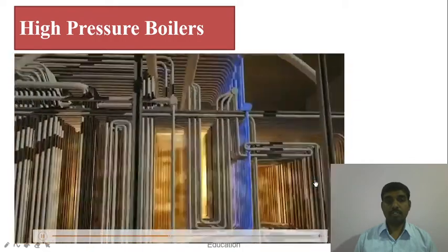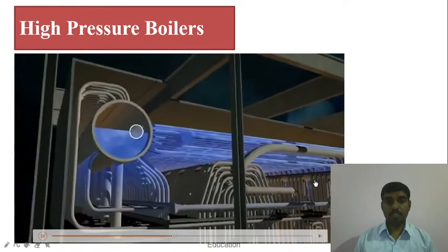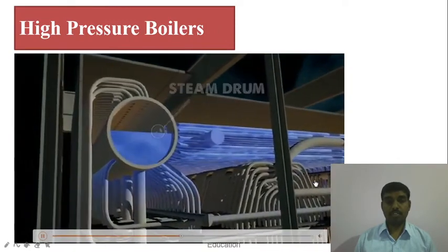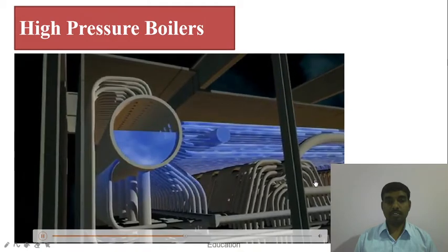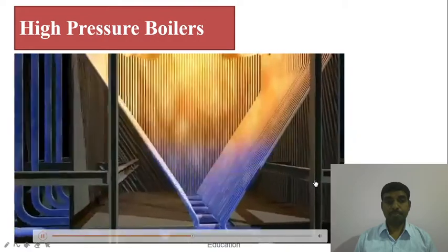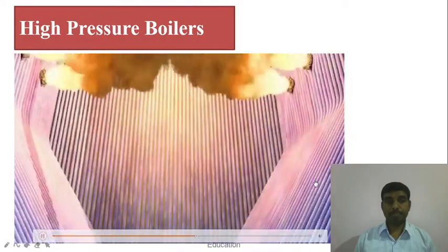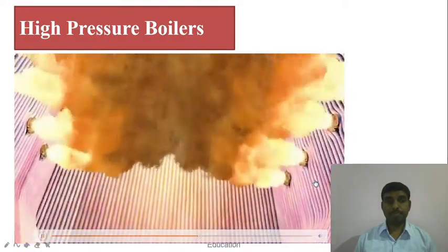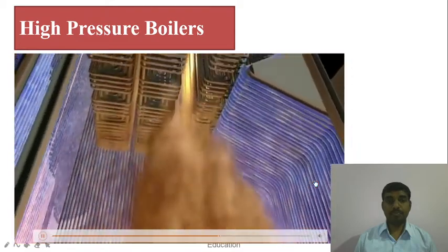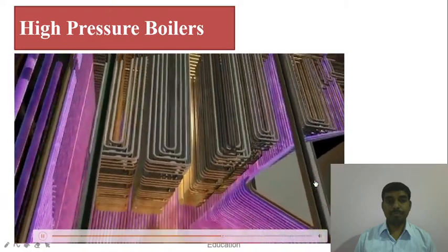Gradually, it's heated to base temperature before gathering at the steam drum, the system's main distribution hub for circulating water and steam through the boiler. Liquid water flows through large downcomers and into the base of the firebox. A network of 2-inch tubes lines the firebox walls, and burners force-feed a continuous supply of combustible fuel into the ultra-hot firebox. Eventually, the insides of the firebox burn so hot that its surrounding steel walls would melt if not for the tube-lined walls of liquid water.